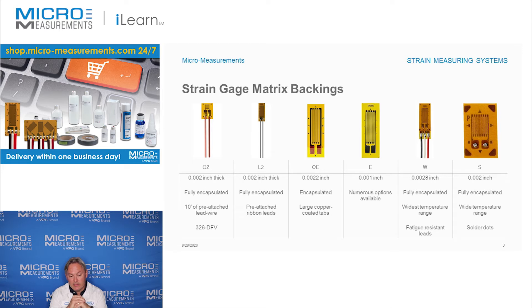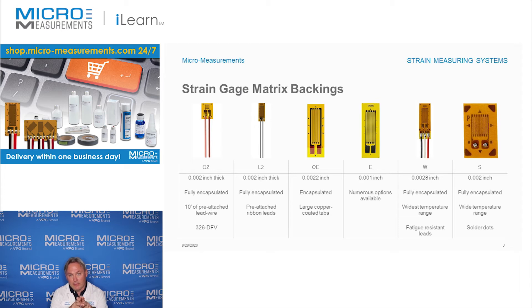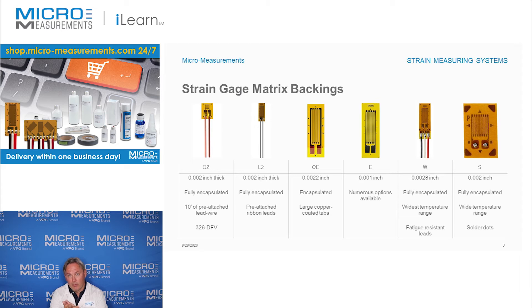E backings are available with a wide variety of options. If you found a gauge with the E backing and wanted to add lead wires to make installation easier, you could do that. The next one is the CE backing, which is the most common one used for experimental testing. The difference between E and CE is that CE has the same initial backing but also has an encapsulating film over the top of the strain gauge, plus large copper-coated tabs to make soldering much easier.